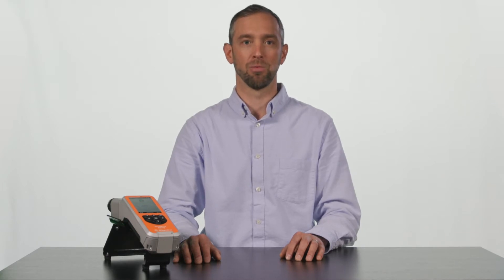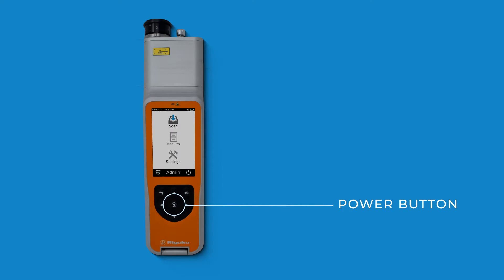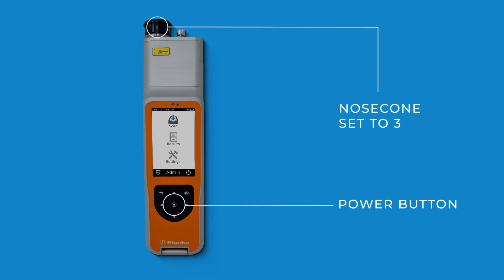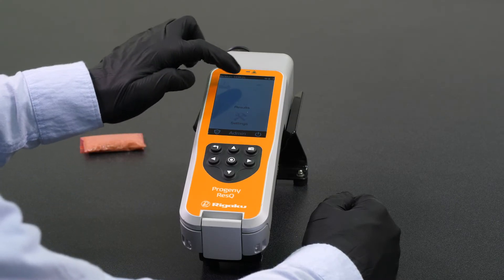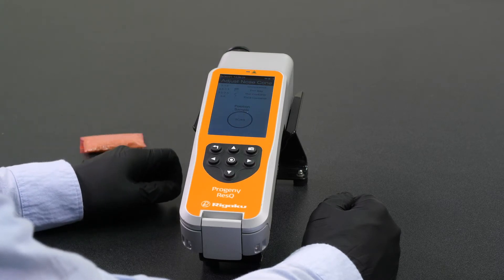The instrument interface is extremely easy to learn and use. Most users become proficient with the ResQ very quickly. The power button is located here, and then with the nose cone setting set to 3 and the sample flush against the nose cone covering the aperture, let's start the scan sequence. Select Scan, select Arm Laser, and select Scan.